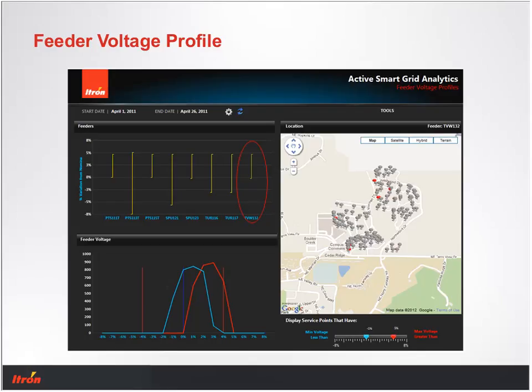In general, we're looking at a slice of time - in this case, a month back in April, set at the top. The upper left-hand quadrant shows about 8 or 9 feeders we're interested in, and that's the voltage bounds, or operating band, these feeders have seen - the lowest and highest voltage measured at any service point on the feeder during that month. Right about in the middle is nominal voltage.